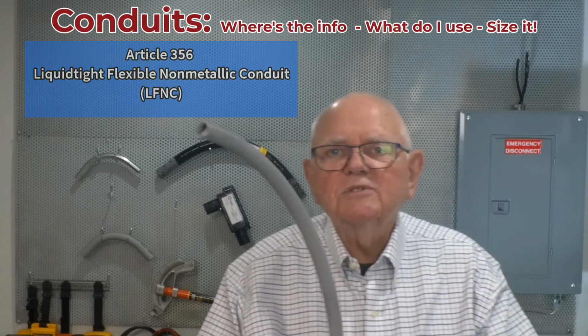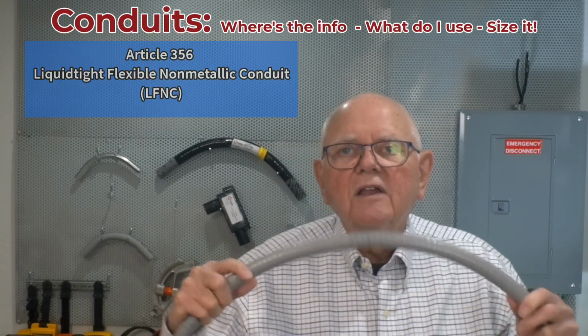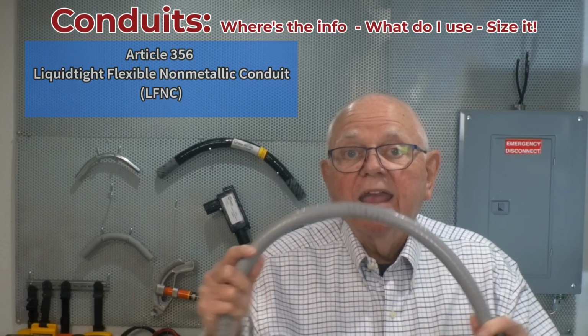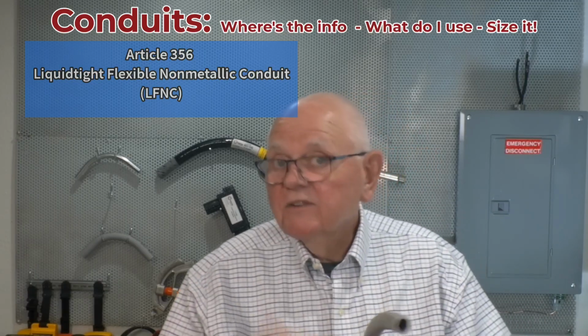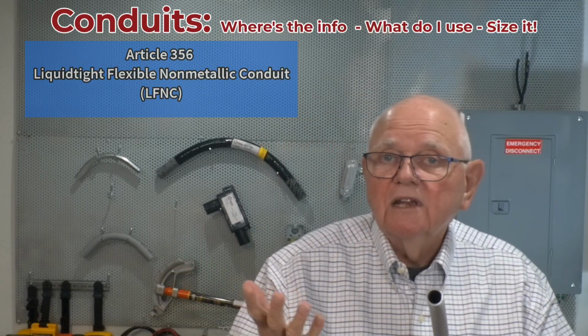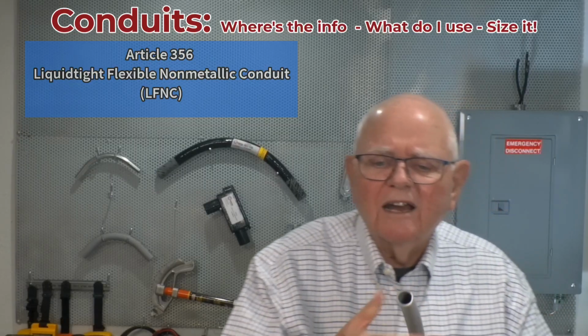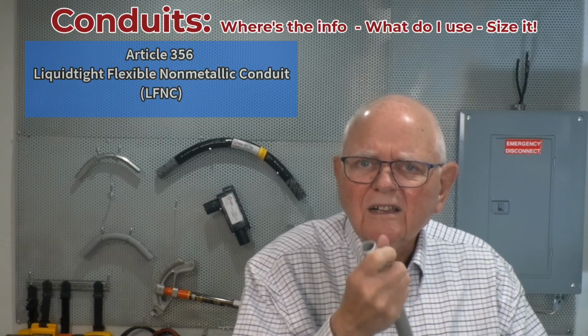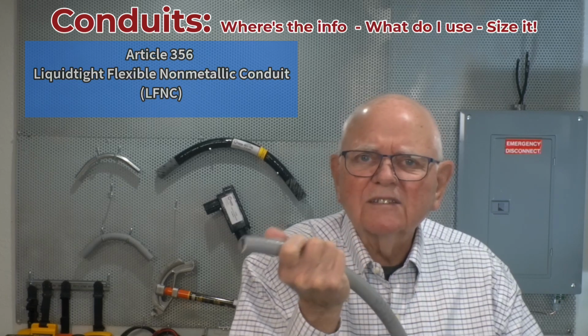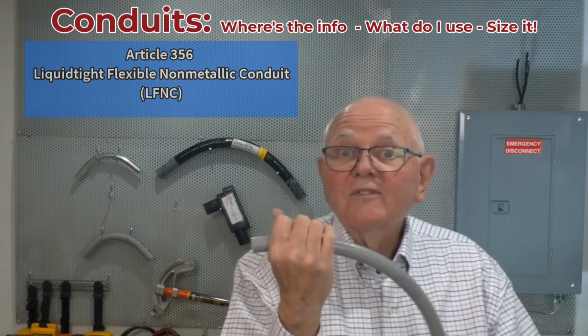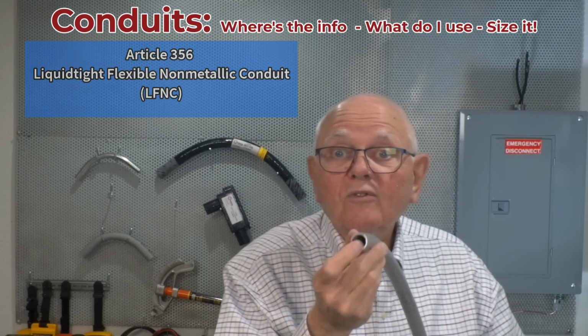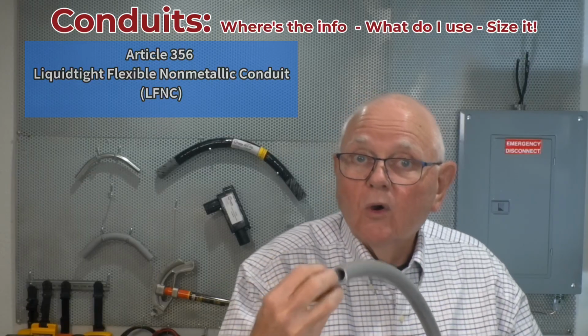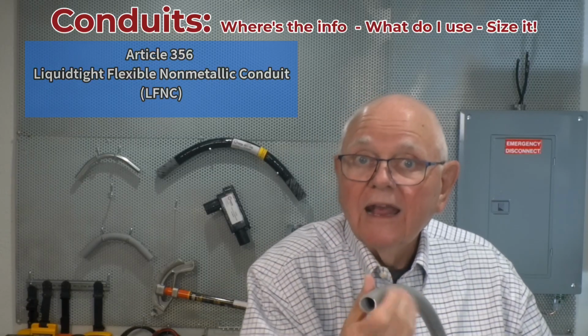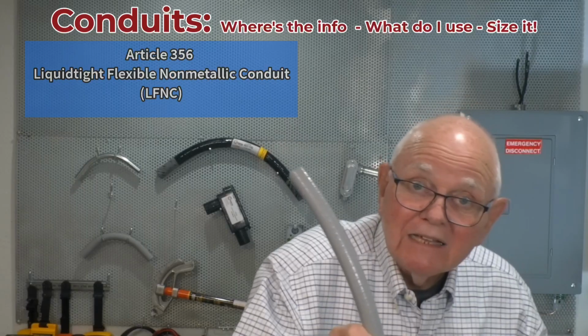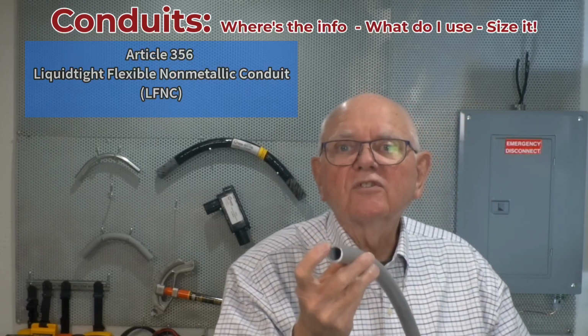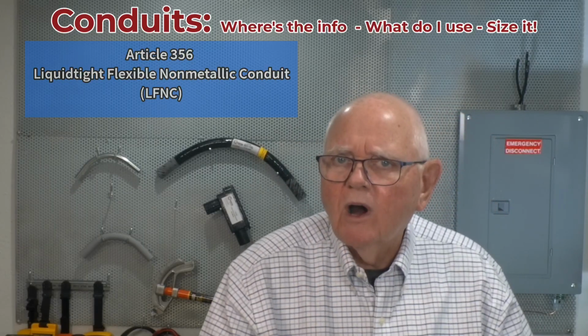So there are 3 types of this liquid tight flexible non-metallic conduit, types A, B, and C. And the 3 types are talking about the support on the inside when they construct the conduit. Okay, so LFNC-A has 1 or more reinforcement layers between the core and the outer covering. LFNC-B, which this is, has an integral reinforcement within the raceway wall.